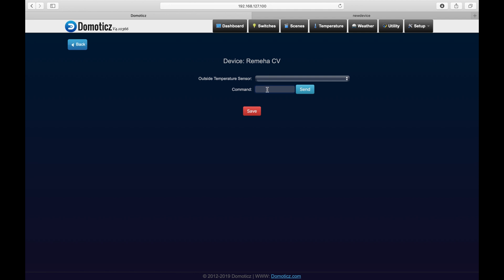And now there's two options you can choose from. And within the Command field, you need to fill out the command AA=28. And press Send. This will send a signal to your heating system, which automatically gives return values on your return water temperature.